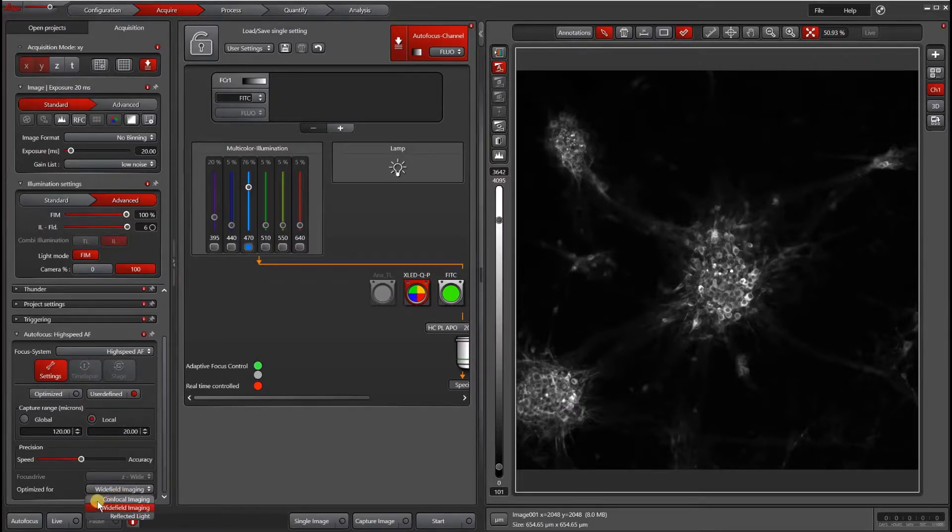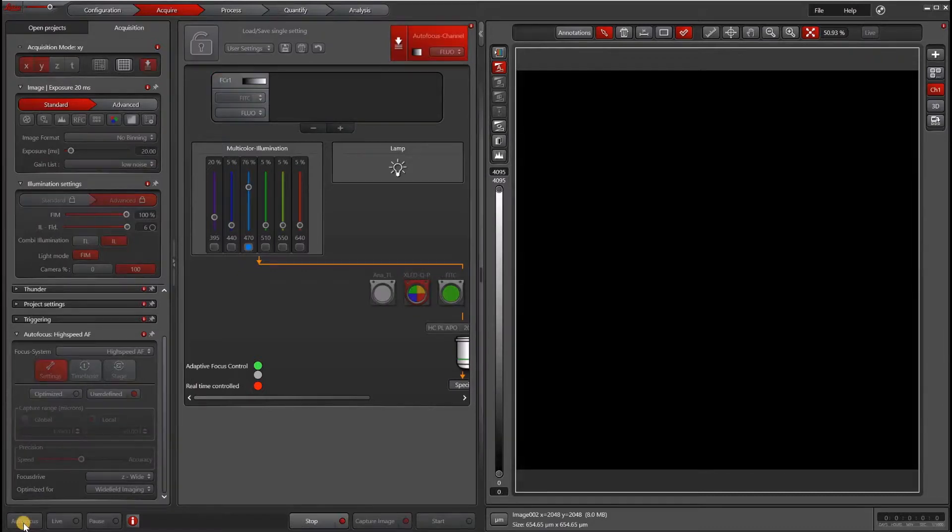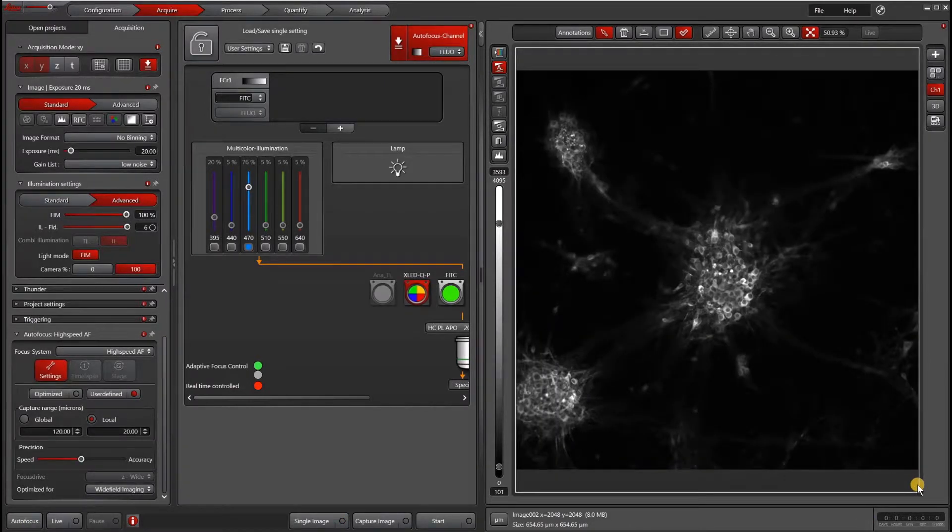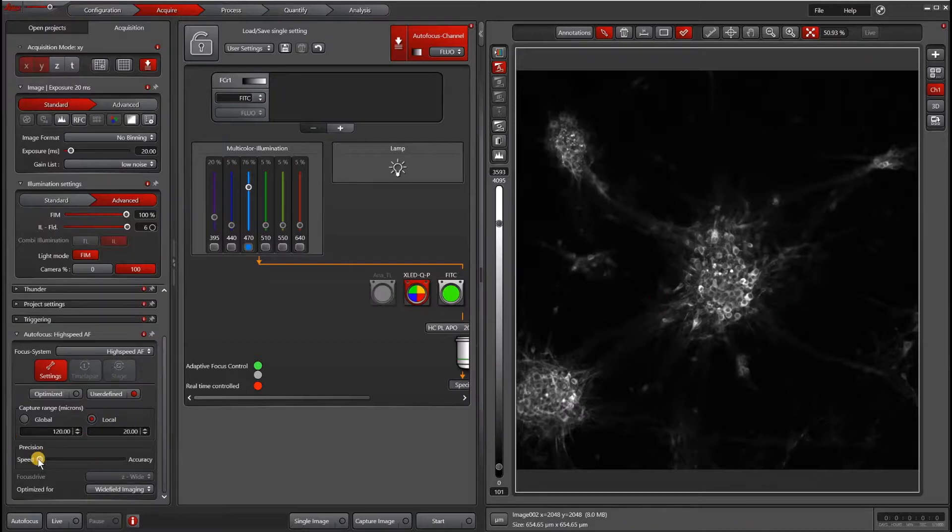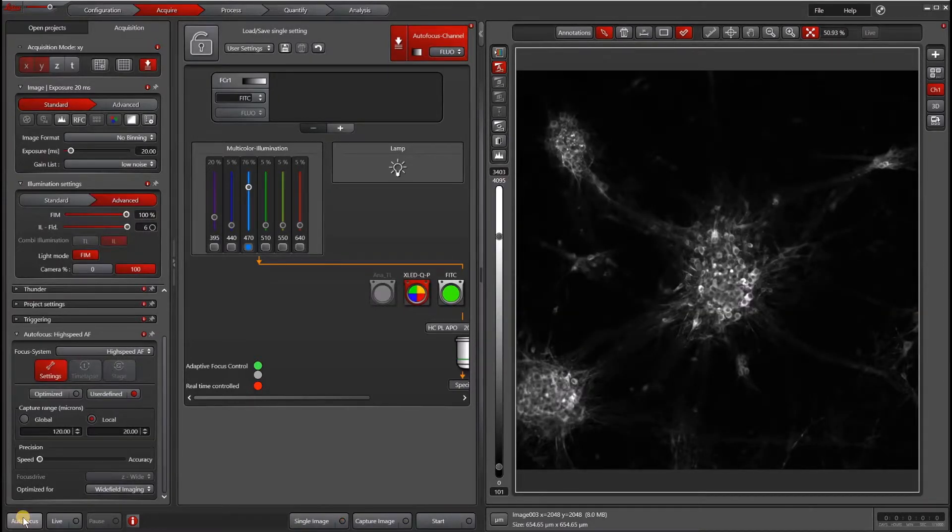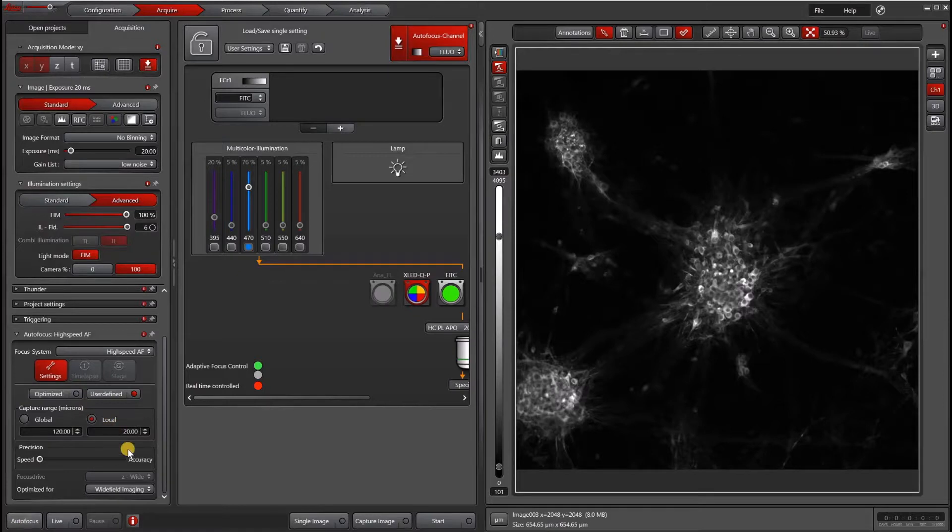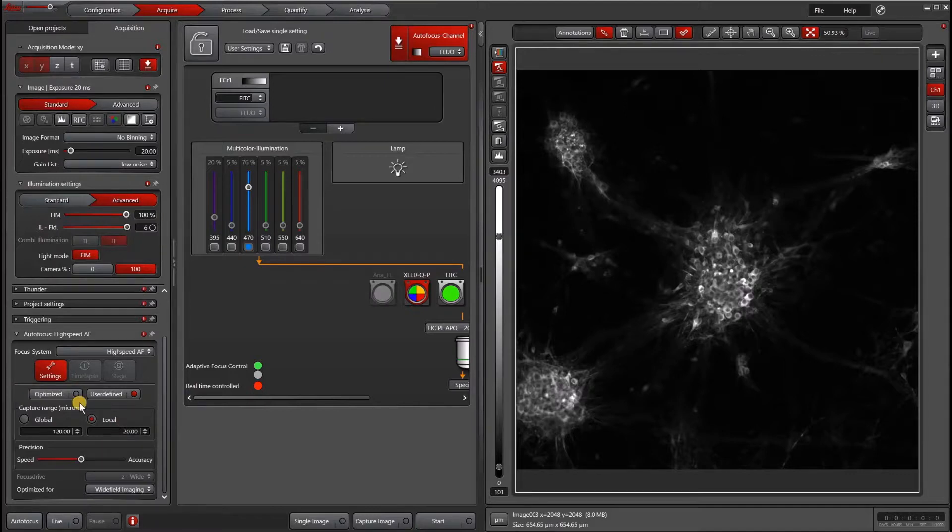To test your settings, go ahead and click the autofocus button in the bottom left-hand corner. It will run a quick Z-Stack. You can see it came up with 23 and the image that it ended up choosing was in focus. Now it doesn't keep that Z-Stack, it only shows it to you temporarily. Just for fun, I'm going to go to high speed and let's do autofocus again. There it only did eight Z-Stacks. But since I was pretty much within range, it did a pretty good job. But you do want to think about the fact that across your sample, you might have a bigger variation than 20. So you could keep the speed at high but also increase your local range such that you have a better chance of getting an in-focus image.